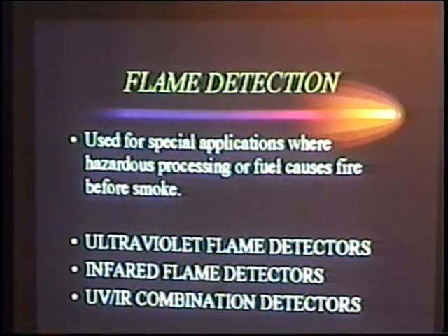Flame detection is a specialized area, used for special applications where hazardous processing or fuel causes fire before smoke. Different applications include storage rooms, control rooms, and building fires. There are three basic types out there, and keep in mind with all these different detection devices, there are numerous types, but the most common are ultraviolet flame detectors, infrared flame detectors, and a UV/IR combination flame detector.